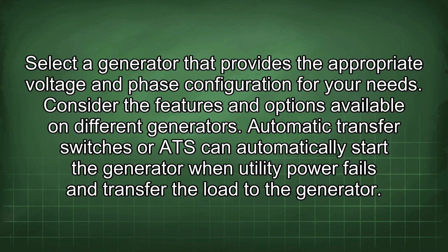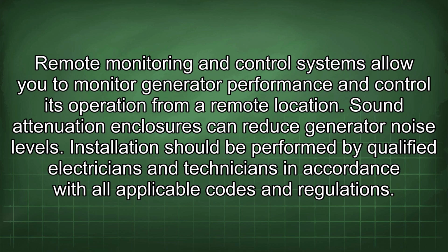Consider the features and options available on different generators. Automatic transfer switches, or ATS, can automatically start the generator when utility power fails and transfer the load to the generator. Remote monitoring and control systems allow you to monitor generator performance and control its operation from a remote location. Sound attenuation enclosures can reduce generator noise levels.